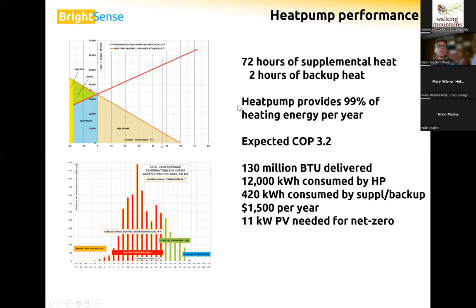And so when I plug in the coefficient of performance, based on this weather, it gives me a COP of 3.2. That means for every kilowatt hour that we pay for, we get 3.2 kilowatt hours of usable thermal energy delivered to our house, 320% efficiency. Some more numbers. This particular example had 130 million BTUs delivered to the home. The heat pump would consume 12,000 kilowatt hours to generate these 130 million BTUs.